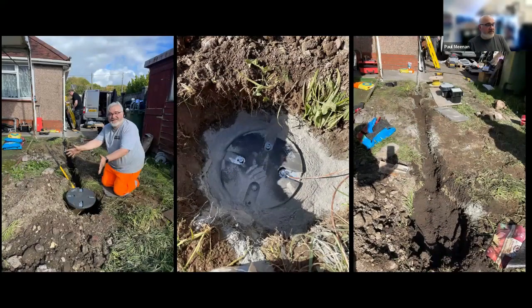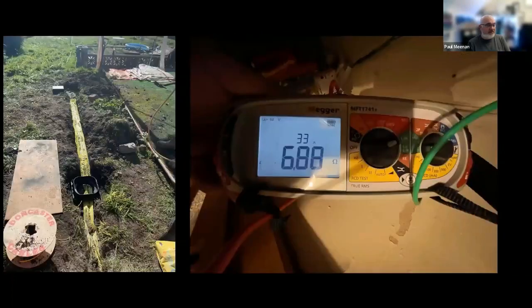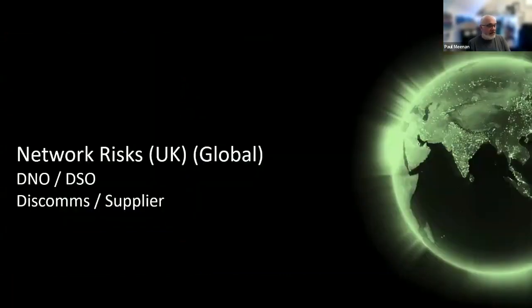And what we were doing is we were replacing a very good friend of mine's earth electrode, which had rotted and corroded. So we put 2 discs in, dug a small trench, bare cable, and we got some fresh soil, covered it up. We got 6.8 ohms, which is very good considering, you know, your recommended 200 ohms. So that's pretty stable, pretty good. And that was a job I did recently in the last year or so.